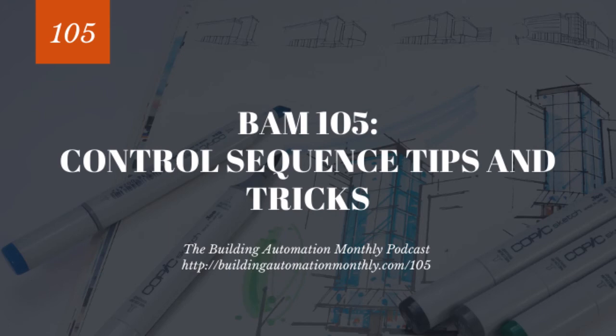doesn't sound right. We walked over to it, and sure enough, the pressure drop across the pump was huge because there was such a buildup of pressure and then there was no water getting through because that balancing valve was shut. And I guess during some sort of maintenance or something, the valve was shut, and then an isolation valve was slightly cracked. And all of this led to this pump not getting enough flow in the secondary loop, which thus it wasn't overcoming the primary's pull on the decoupler, so it wasn't pulling flow to the secondary loop from the primary, and thus all the valves on the air handlers were wide open. I mean, this was nasty. After we got it fixed, we had to go retune loops because these loops had tuned themselves to being wide open. It was just kind of craziness.